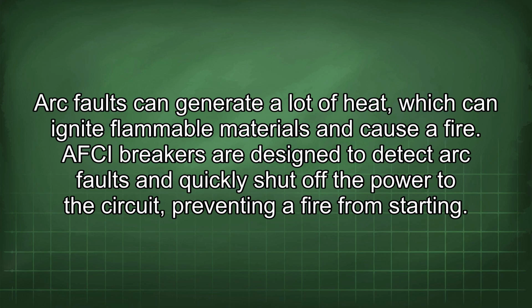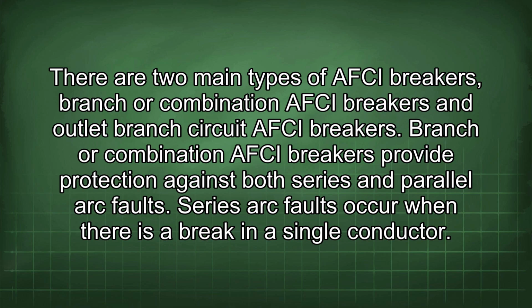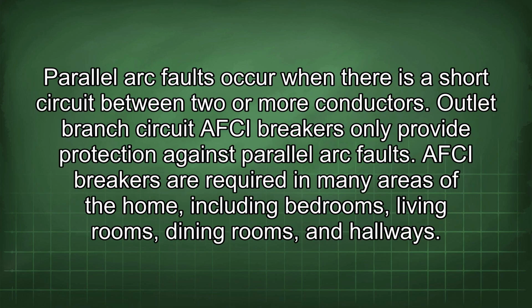There are two main types of AFCI breakers: branch or combination AFCI breakers and outlet branch circuit AFCI breakers. Branch or combination AFCI breakers provide protection against both series and parallel arc faults. Series arc faults occur when there is a break in a single conductor. Parallel arc faults occur when there is a short circuit between two or more conductors. Outlet branch circuit AFCI breakers only provide protection against parallel arc faults.